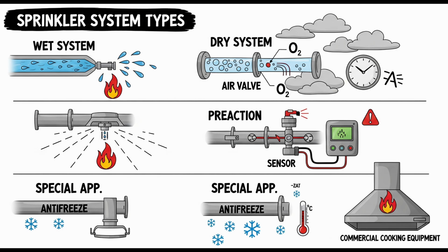The low pressure signal is set at a minimum of 5 psi above the calculated trip pressure. So it warns you before you actually hit the pressure where the valve might trip. Exactly. It indicates that pressure is getting critically low. The high pressure signal is set at 5 psi above the normal system air pressure, signaling that pressure is potentially too high, which could stress components or maybe even slightly delay tripping, though the main concern is usually low pressure.